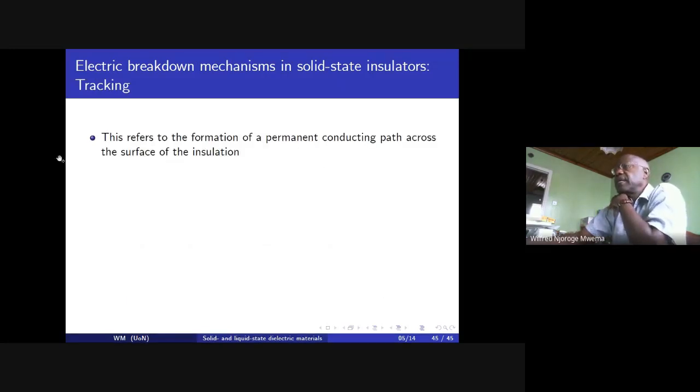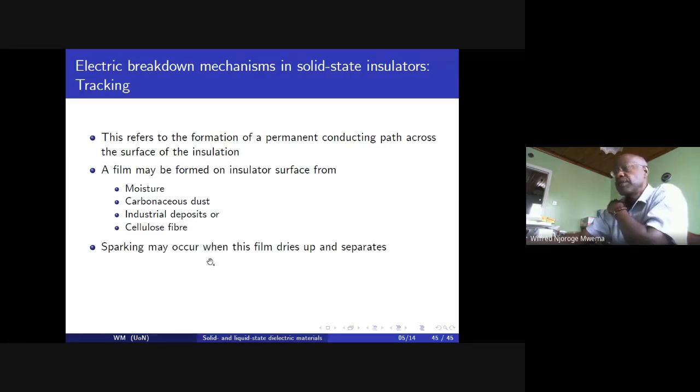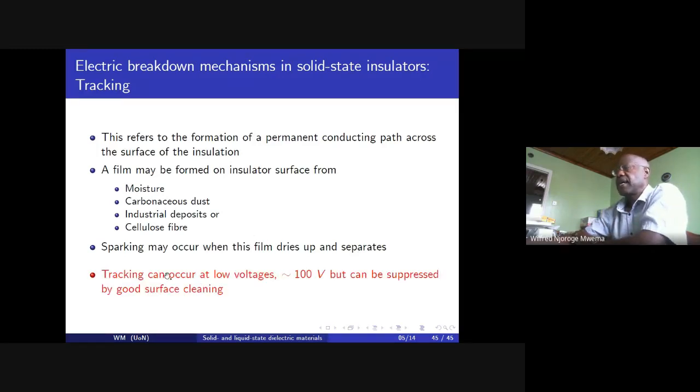Tracking itself refers to the formation of permanent conducting paths across the surface of the insulation. So a film may be formed on the insulator surface from, one, moisture; two, carbonaceous dust coming from the environment, industrial deposits, or cellulose fibre. Sparking may occur when this film dries up and separates.